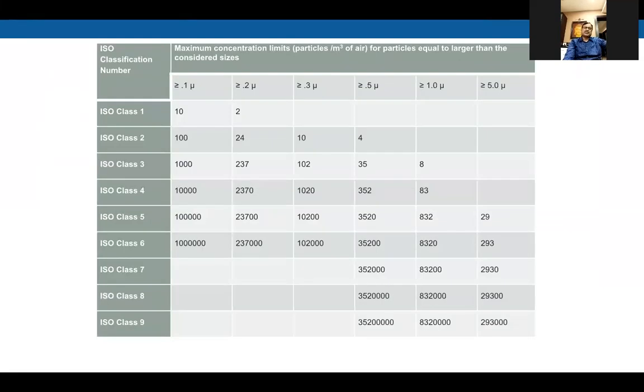So this is the ISO class 5, which is a requirement of our modern day OTs, and up to ISO class 6 also we have permitted. So this is basically a particulate count. The particulate count has to be according to this criteria. Class 100 is also plotted against this, class 100 versus class 1000 OTs, which are American standards. So this is just a grid to show you the particulate count, that is 3520 particulate count of 0.5 microns and larger is our standard for ISO class 5 operation theaters. Next, please.